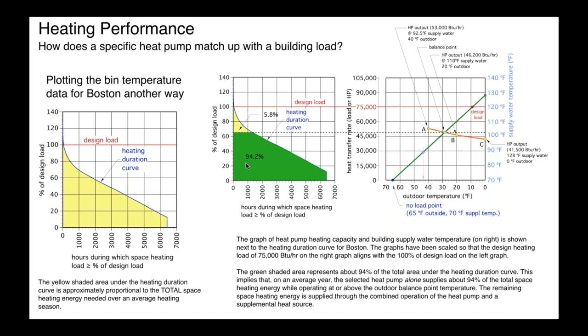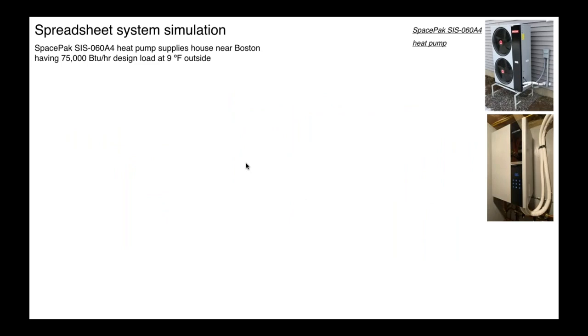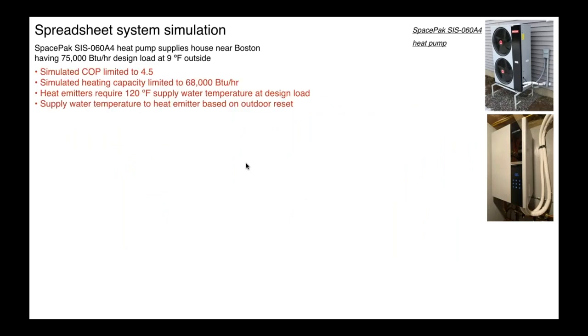And that's one of the nice things about plotting a heating duration curve. We could look at other interpretations of that heating curve. If we size the heat source, for example, for half of the design load, how much of the total space heating energy could a heat source sized for half of the design load provide? It's definitely more than half of the total space heating energy. And again, the underlying reason is in most climates, we spend a lot of time not at design load conditions, but substantially warmer, okay? Now, putting all this together, we built a spreadsheet.